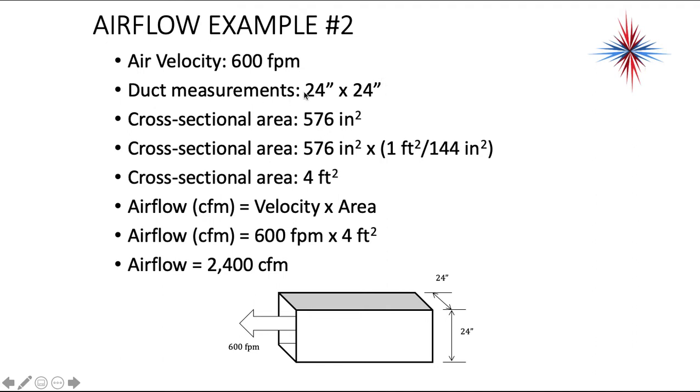So let's take this. Then we multiply it out. 24 by 24 cross-sectional area is 576 inches squared. We have to get this to square feet. So we know there's 144 square inches in a square foot. We take it to cross-sectional area 4 square feet.